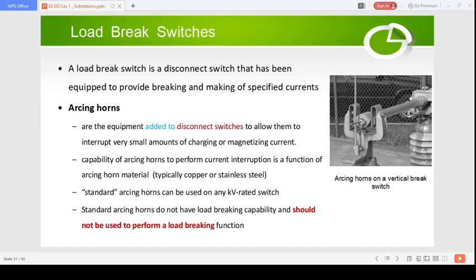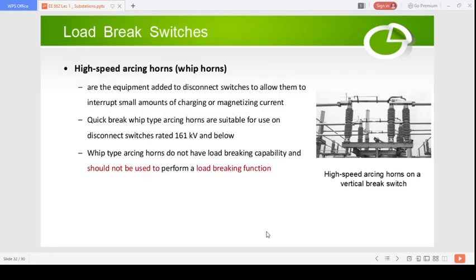Okay, so the standard arcing horns can be used on any kV rated switches or isolators. The standard arcing horns do not have load breaking capability, so keep this in mind. Just connecting the arcing horn to the isolator won't make that isolator capable of disconnecting the load current. It's not for that purpose. These arcing horns do not have load breaking capacity, so they should not be used to perform a load breaking function. You need to keep that in mind.